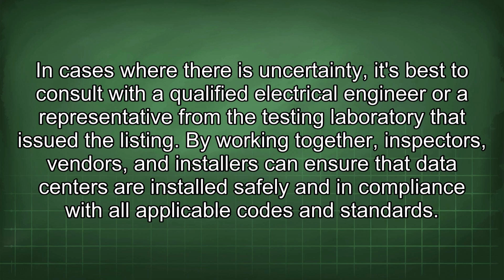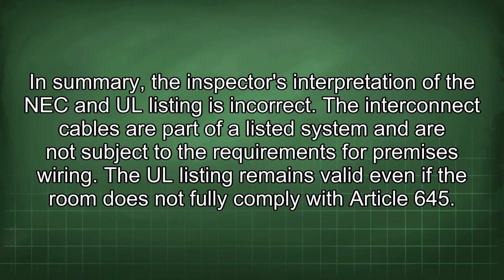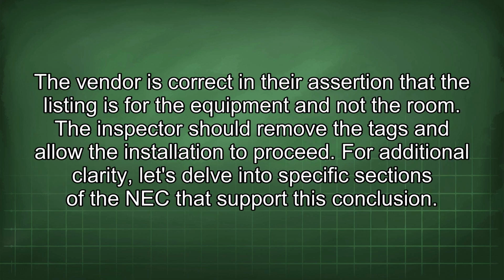By working together, inspectors, vendors, and installers can ensure that data centers are installed safely and in compliance with all applicable codes and standards. In summary, the inspector's interpretation of the NEC and UL listing is incorrect. The interconnect cables are part of a listed system and are not subject to the requirements for premises wiring. The UL listing remains valid even if the room does not fully comply with Article 645. The vendor is correct in their assertion that the listing is for the equipment and not the room.